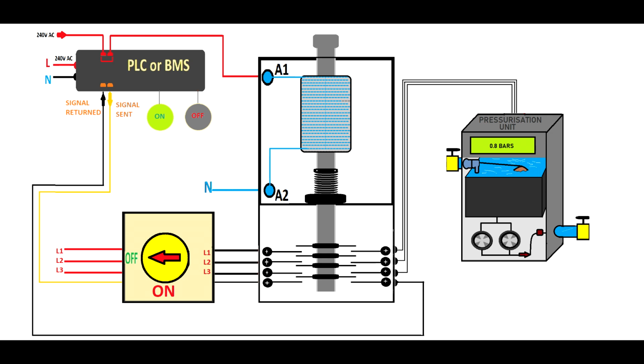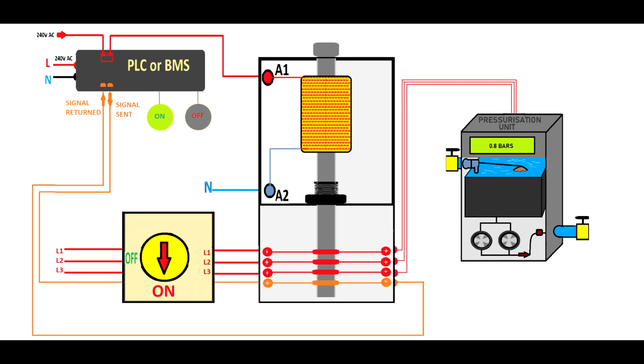As you will see, the signal is not passing by because the circuit is interrupted. And when this happens, the signal is not coming back into the programmable logic control. I have sometimes found the pressurization unit having a separate power supply and only sending inputs to the PLC. But this is one of the rare cases where I found this type of mistake. Now you will turn on the isolating switch, and then the signal will go back into the PLC. You see, the signal goes and the signal comes back. This is wonderful. Everybody is happy. We have a perfect signal.